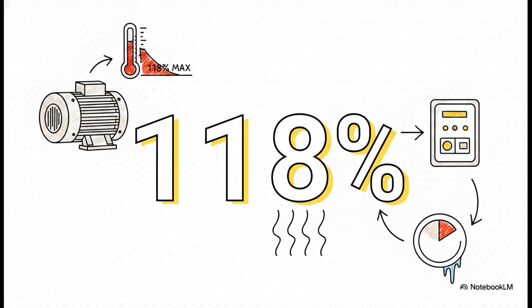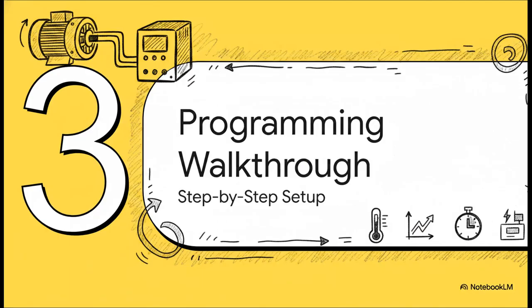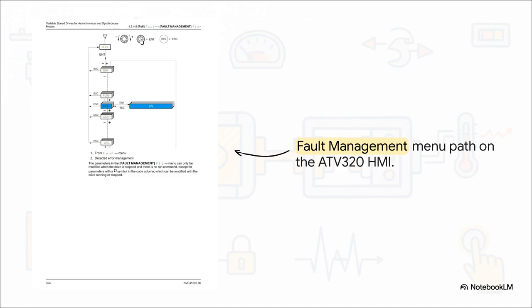By default, the ATV320 will trigger a detected error and safely trip the drive when the motor's internal thermal state hits exactly 118% of its rated state. And it's smart too. It'll prevent the motor from restarting until that thermal state cools back down below 100%. Think of it as a built-in mandatory cool-down timer. Now for Section 3, a step-by-step programming walkthrough. Let's step right up to the display.